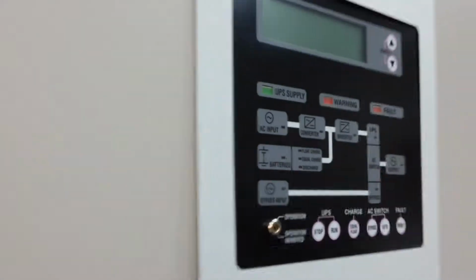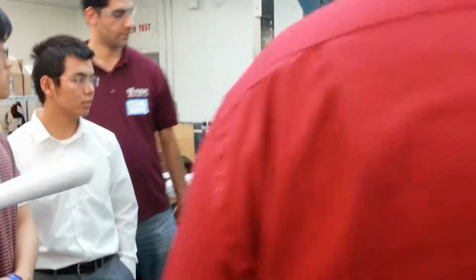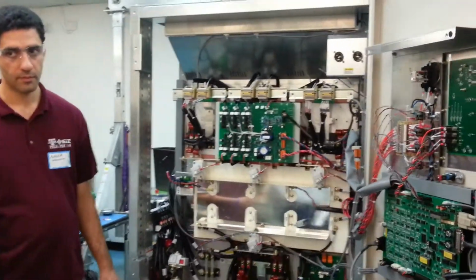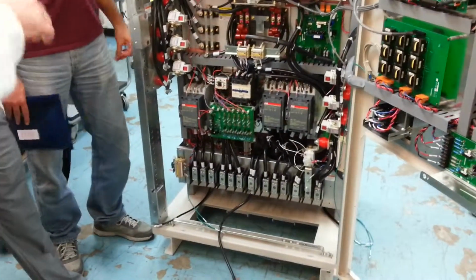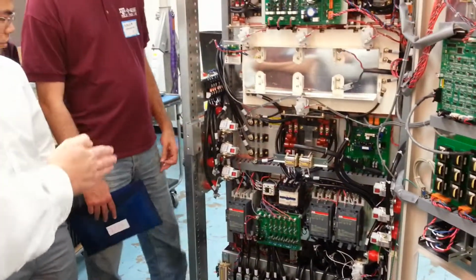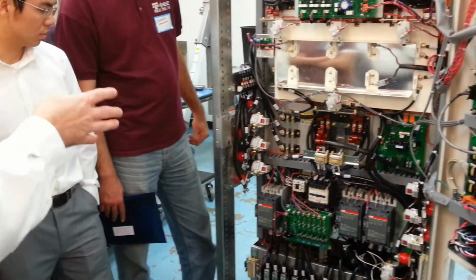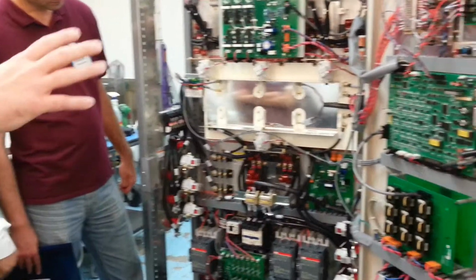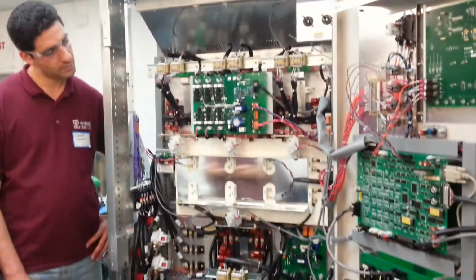Okay? We can go back around up to the front and take a little look at it. Now this one isn't a double conversion. This is what they call a rectified front end, kind of like a drive. Input on the bottom, input contactor. There's rectifiers right there on the left side next to the fuses. That's your rectification. Comes in, goes to the unit, powers up the bus. The inverter is in the top section there.